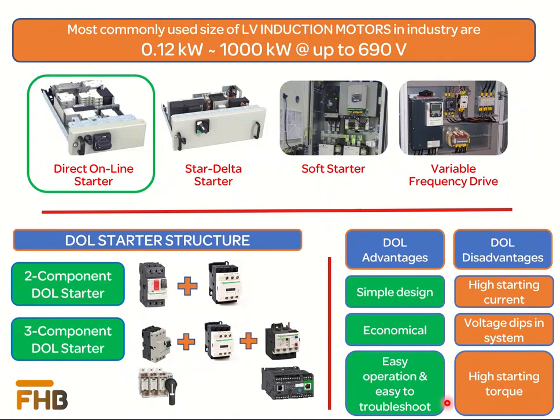A DOL starter in low voltage motor control centers can be designed either with 2 power components or with 3 power components. In the 2 power component design, the motor protection circuit breaker provides the thermal magnetic protection, and the magnetic contactor controls motor starting based on defined logic. In the 3-component starter, a circuit breaker or fuse isolator provides the magnetic or short circuit protection.